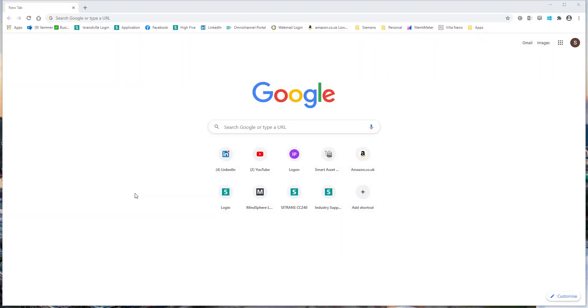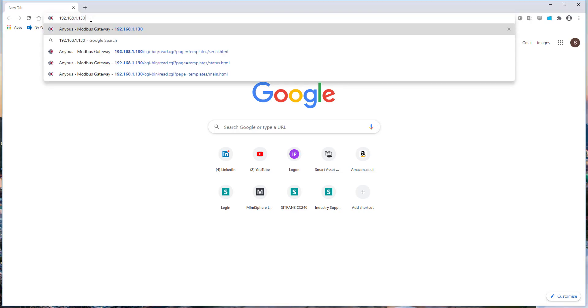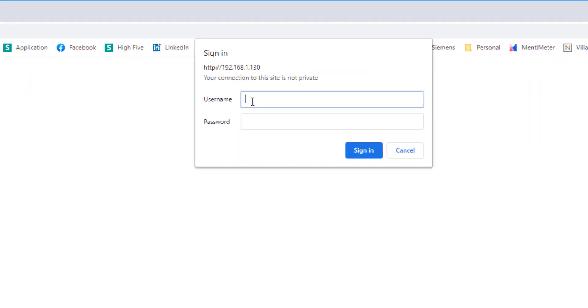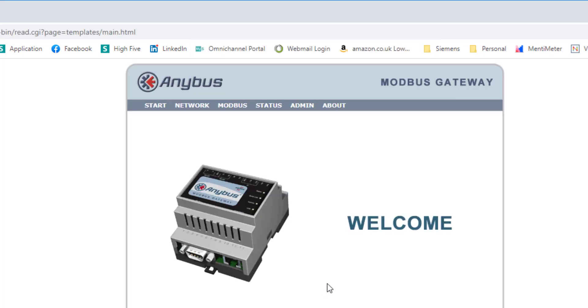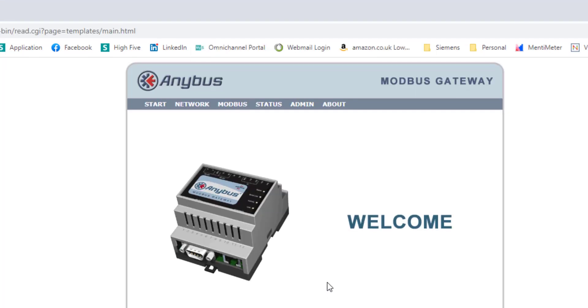When the gateway is shipped, it comes with a default address. If you go onto the HMS or Anybus website, there is a free tool to download to change the IP address. But I've already done that. In this case, my IP address is 130 and my domain is 1. So you need to make a note of that because you're going to need to set up the serial converter with that information. The default password is admin and admin. Of course, I would recommend that you change that once you've configured this for the first time.